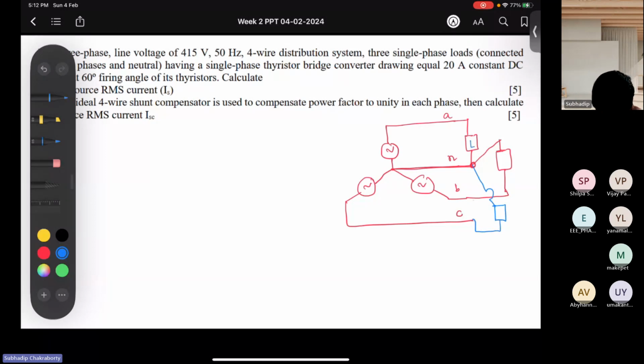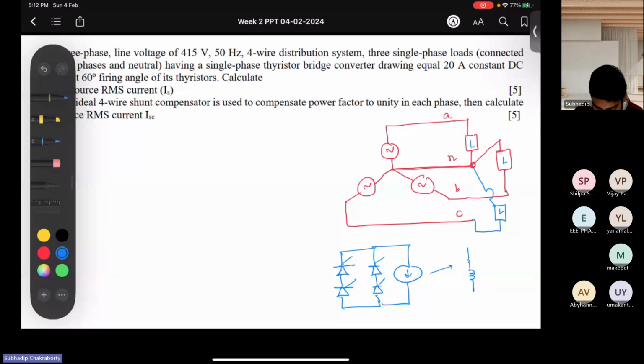Now, each of these loads, how do they look? They are single phase thyristor bridge converters with constant current loads. You can model these as RL loads where the L is very large. That's why we can model it using a current source. And you have your live and neutral going here, for each of the phases, drawn like this. So this is, I can say, L and N. For every phase you have this kind of load connected, so phase A, phase B, and phase C all have single phase loads of this nature.